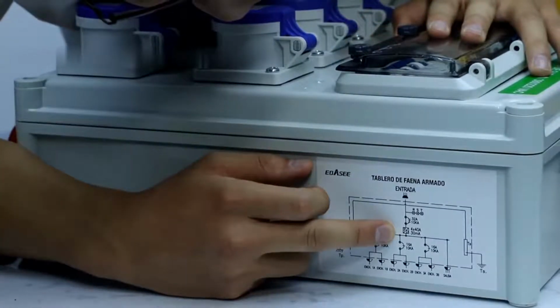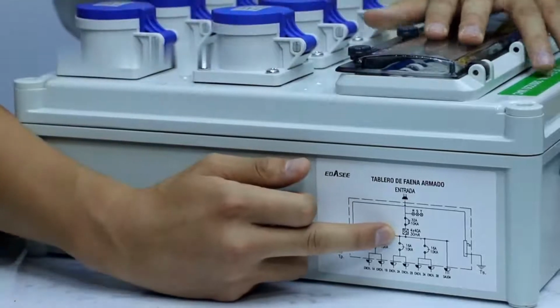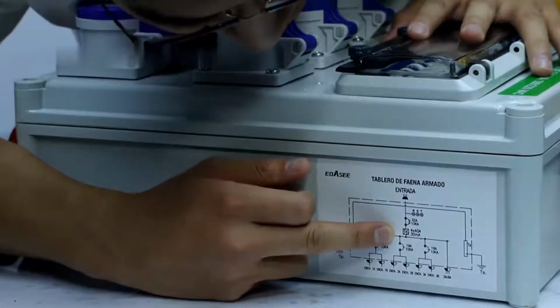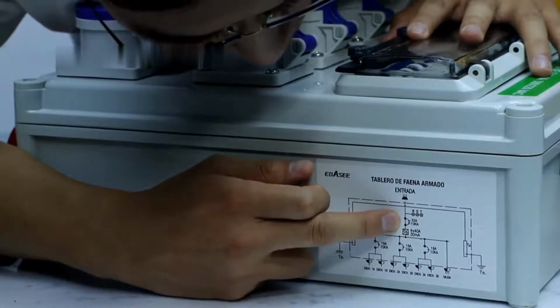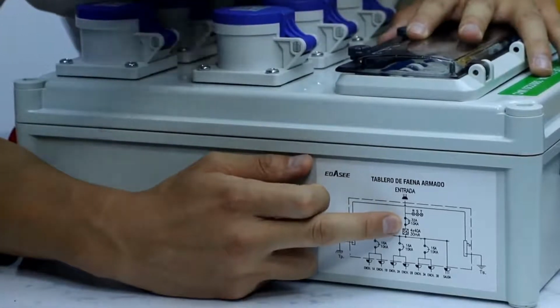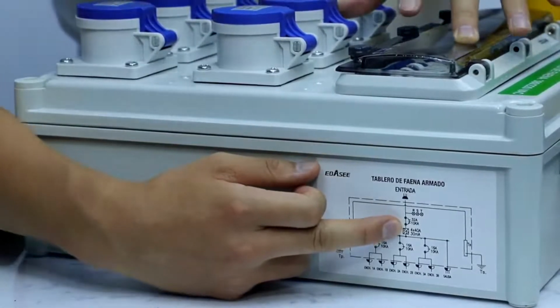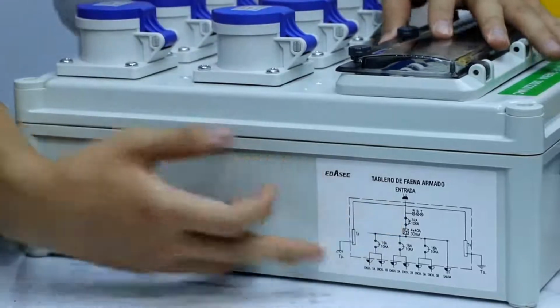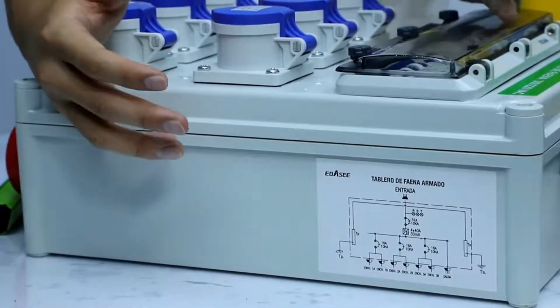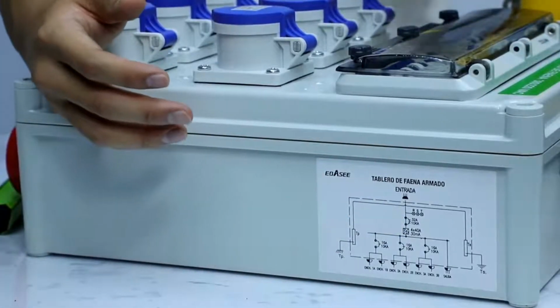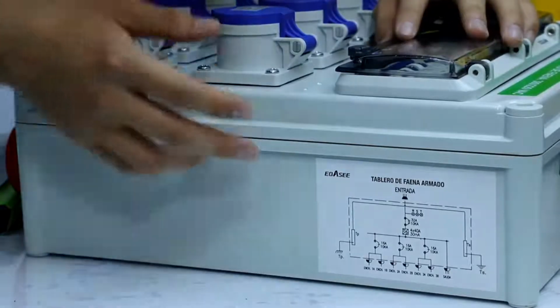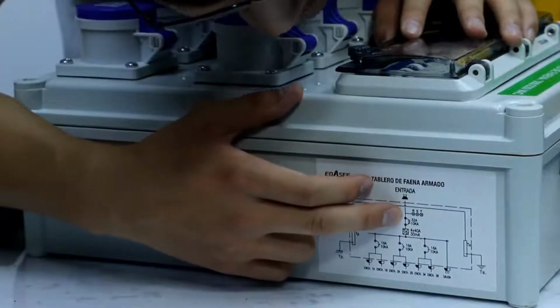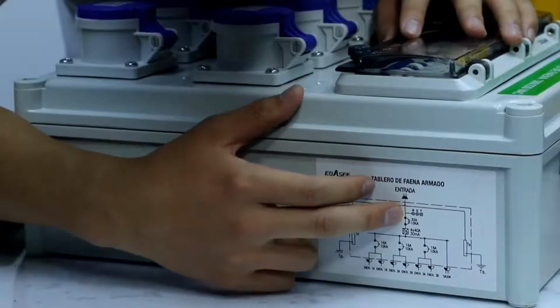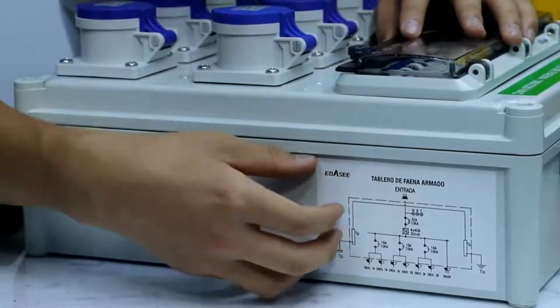The residual current is set at 30 milliamperes. And above will be a 3 pole, 32 amperes, 10K miniature circuit breaker. It can also be replaced by an isolator or fuses, anything you like, to protect the whole system. And up here will be 3 indicator lights that show the condition of the 3 phases.